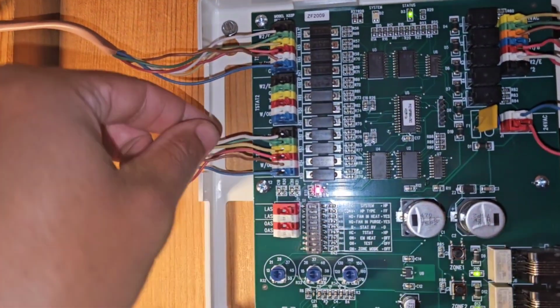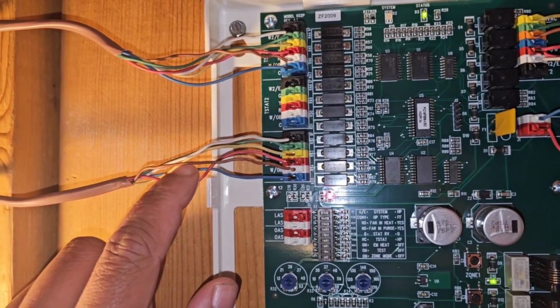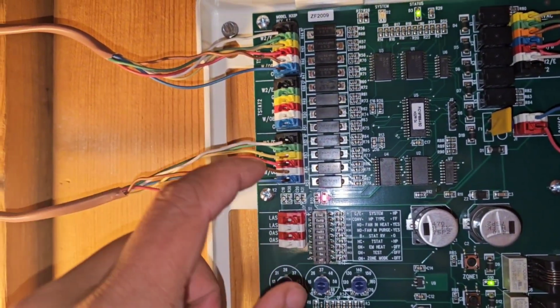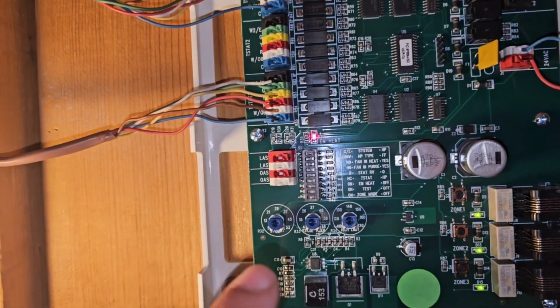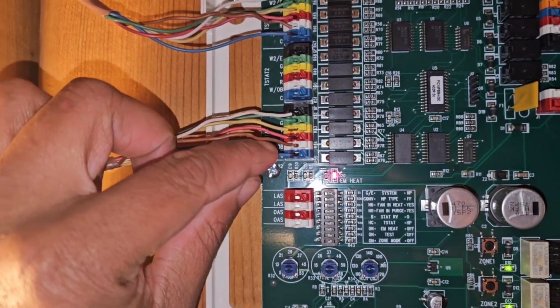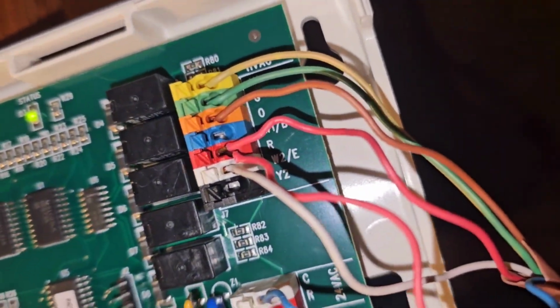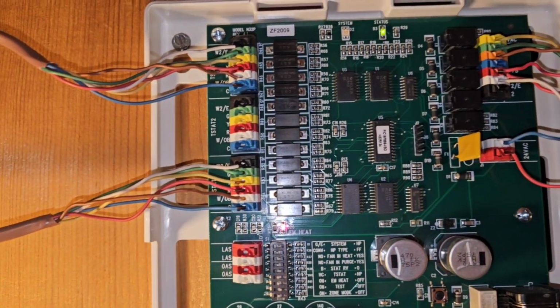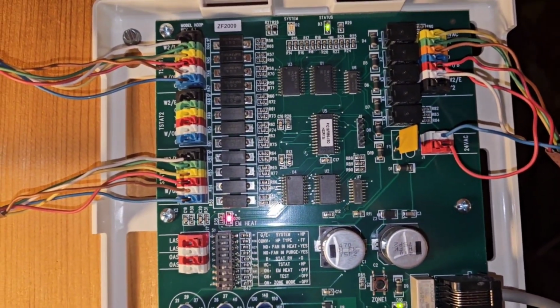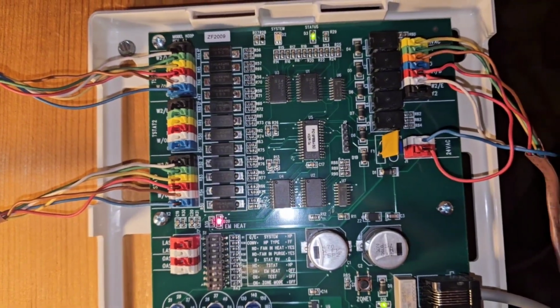Now I want to show you what I missed that some people on YouTube would have probably noticed the moment the video first started. They had the W wire and the brown wire they're using for the reversing valve swapped. That's why we couldn't get the heat strips on. Even though I had the board programmed for it, the W was in the reversing valve spot here on both thermostats, but over here it's set for the W2 emergency terminal. So swap that around. Hopefully now, waiting for this thing to get out of delay, it should kick on with no problems, and we should get the emergency heat to kick on.